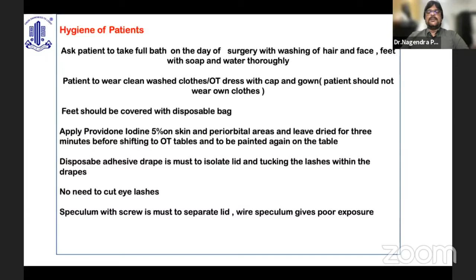And there is no need to cut the eyelashes. And when you use the speculum, it should be a screw type that pulls the lid wide open, and it reduces the chance of lashes coming into the operating field. A wire speculum gives poor exposure, so it should not be used except in inpatient or pediatric cases.